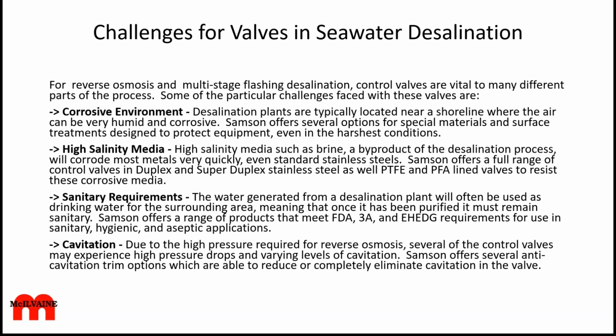Please feel free to make a comment at any time, but basically Samson is offering several options for corrosive environments, special materials and surface treatments to protect the equipment in the harshest conditions. For high salinity media such as brine, most metals would corrode very quickly, even standard stainless steels. So Samson offers a full range of control valves in duplex, super duplex, as well as PTFE and PFA lined valves to resist these corrosive media.